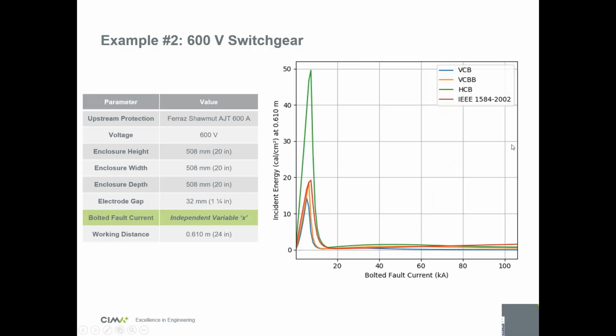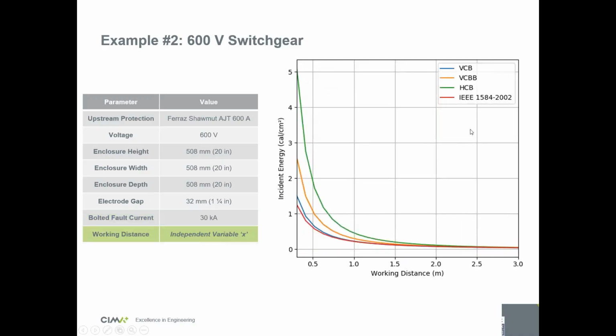So here you see your worst case is very, very much higher for HCB. Then you have the old version of the standard. The HCB would give you 50 calories. The old standard would give you 20 calories. VCBB is about the same. Then you go down, it's VCB at about 15. And you see your worst case is really at about 5 kA in that case. And then you see the working distance. What's the impact? The working distance is still the same inverse square law.